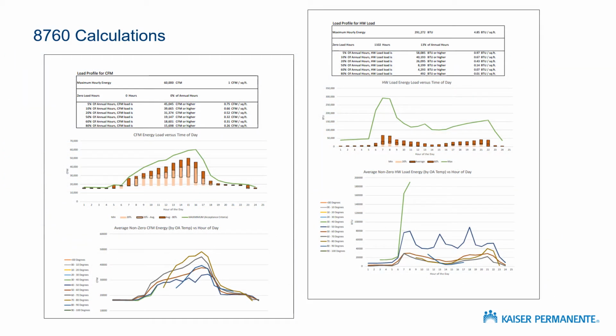And then finally, or I guess third up, are what I call the 8760 calculations. These actually matter a whole lot more than your load calculations. I like to say that in a normal design, we design for the sort of peak hour of summer, and then we design for the peak hour of winter, which means that we've designed for 2 hours of the year, and that leaves us 8,758 hours for which we just don't even have a design. And we can't do that.